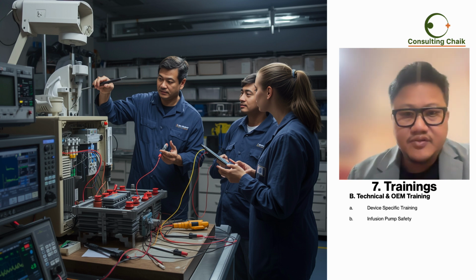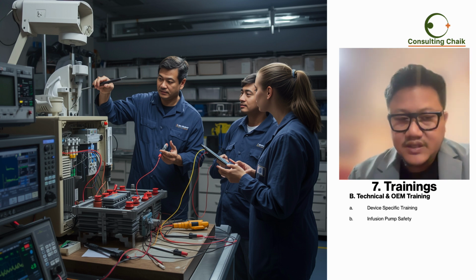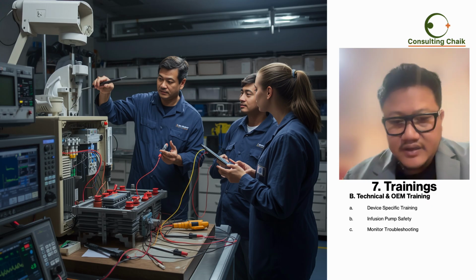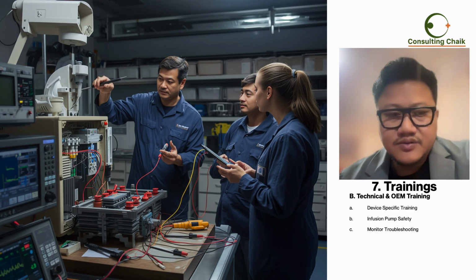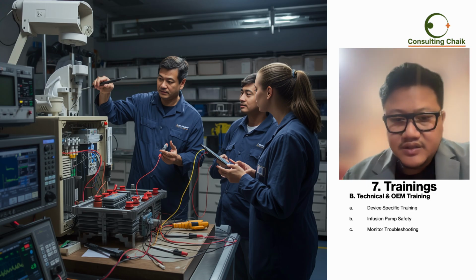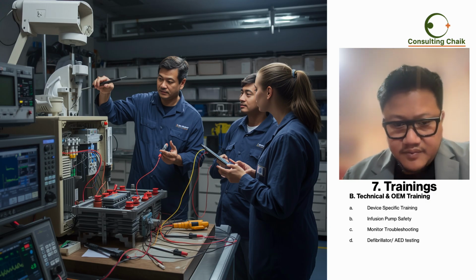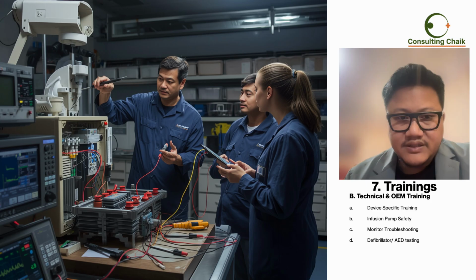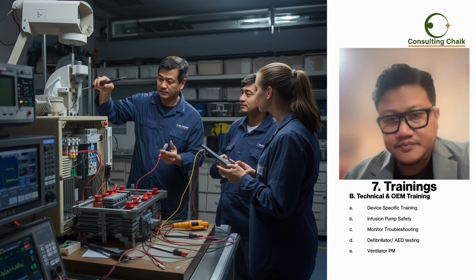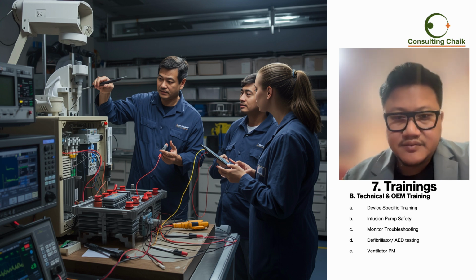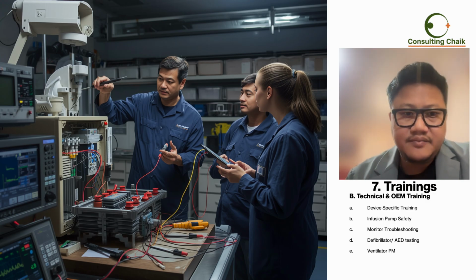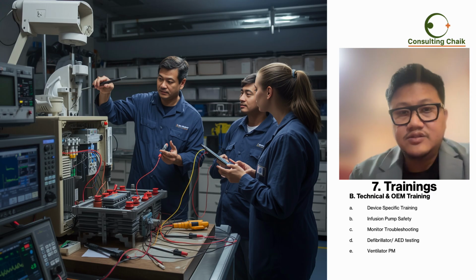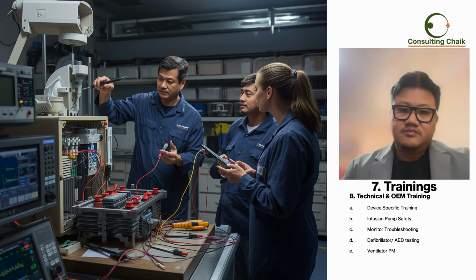Then infusion pump safety. Annually you check the flow, occlusion alarms, all that. These are very vital, critical equipments. That is why individual training for these equipments is required. How do you handle patient monitor troubleshooting? Okay, then for defibrillator, what checks do you need to do on a periodic basis, all that. And for ventilator, original equipment manufacturer hands-on training is required. For ICU, it has to be ICU focused, okay, because it's very vital out there.